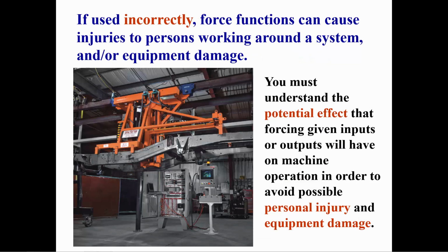It is very important that you do not use forcing unless you completely understand the operation of the equipment and program you are working with. Misuse could cause personal injury and/or equipment damage. Many companies have policies against using the force function. An indicator light will be lit on the CPU module of the PLC when forces are enabled.